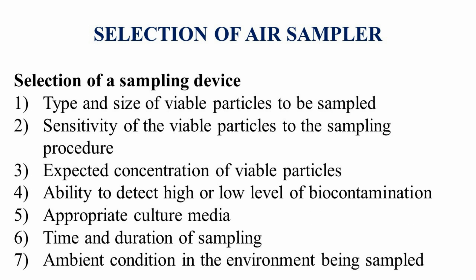Selection of a sampling device. Before selecting the sampler, let's understand the points to be considered. First is the type and size of viable particles to be sampled — the selected sampler should be capable of sampling small as well as large particles. Second is the sensitivity of the viable particles to the sampling procedure; the selected air sampler should be capable of giving correct results when used as per a predefined SOP.